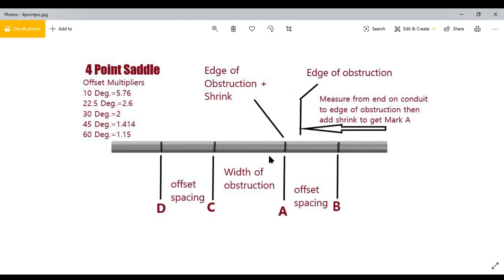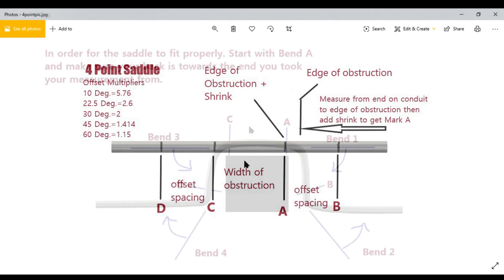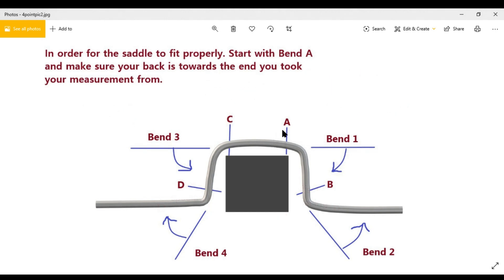What's important with this four-point saddle method is you have to start with Bend A and do them in sequence: A, B, C, and D. There are other ways to bend this saddle. The way I usually do it is bend A, then bend C so I can line them up, then work on the outside bends. With four bends, it's easier to do it that way to avoid dogging it.